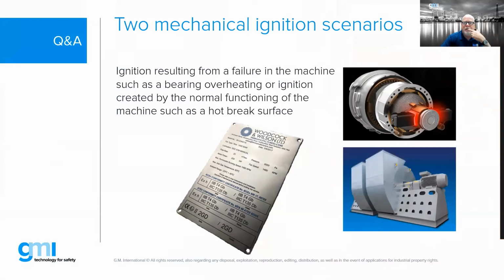So we talked a little bit about what could be examples: ignition resulting from failure in a machine, such as a bearing overheating, a hot surface, or something like that. That label you see in the middle is actually an example of both an ATEX and an IEC Ex certified product with that Ex H marking, and that happens to be a fan. So again, a mechanical piece of equipment that normally we wouldn't think would have to comply with relevant standards. Well, guess what? This manufacturer has gone out, spent the time and money, had it assessed by a third party, and now has a third party certified fan that's Ex H, if you will.